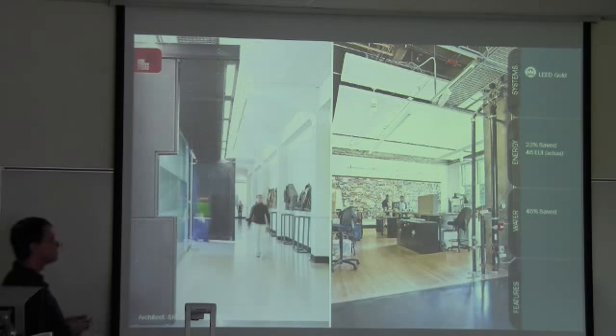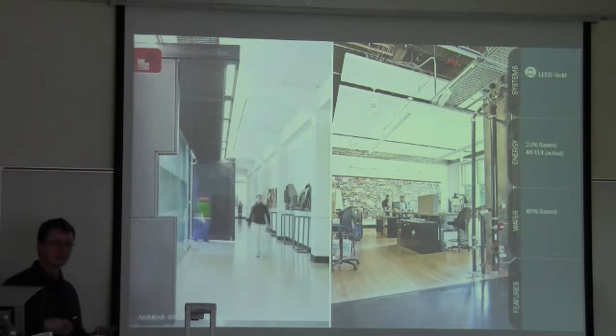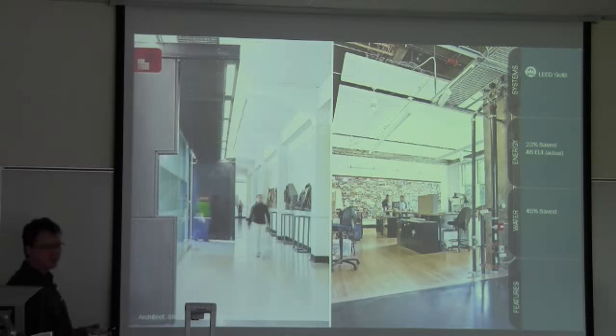This project was being designed at the same time as the Port of Portland project that I'll show you. So we kind of collaborated efforts together in the office as far as evaluating radiant panel manufacturers, looking at different styles of panels, looking at the trade-off for economy and performance of panels. We looked at radiant sails, we looked at chilled beams, we looked at all the different type of elements that can go into a space. Radiant sails and chilled beams are great for cooling and where you have a high cooling application, but not as efficient for heating. And our climate is more skewed, depending on their use, for heating. So it was a nice effect to use that.